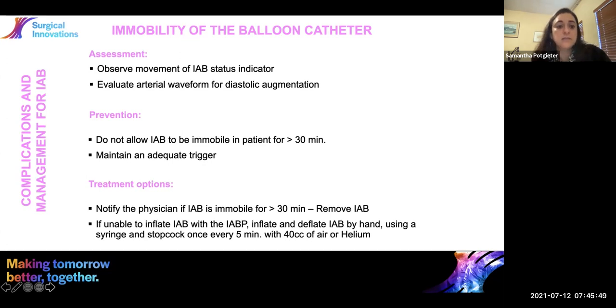So your assessment and the observation of the movements of the catheter must be there, not allowing it to be in the patient immobile for longer than 30 minutes. Your console will warn you. The pump will warn, and it starts counting from a minute. So the minute you put the balloon catheter into standby for whatever reason, there's a counter that pops up on the screen and it tells you that the balloon isn't moving. And it will alarm, and it will continue to alarm to tell you that you need to address it, that there's a risk to the patient for that.